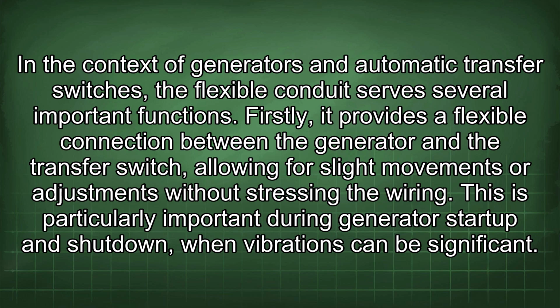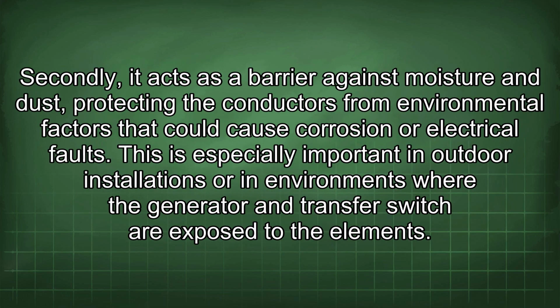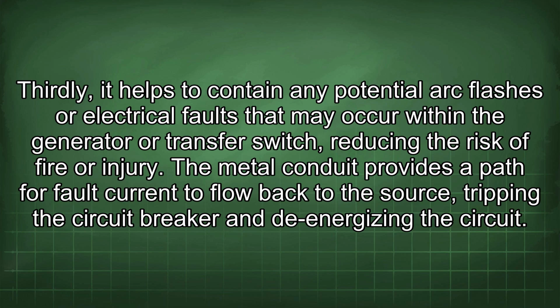This is particularly important during generator startup and shutdown, when vibrations can be significant. Secondly, it acts as a barrier against moisture and dust, protecting the conductors from environmental factors that could cause corrosion or electrical faults. This is especially important in outdoor installations or in environments where the generator and transfer switch are exposed to the elements. Thirdly, it helps to contain any potential arc flashes or electrical faults that may occur within the generator or transfer switch, reducing the risk of fire or injury.